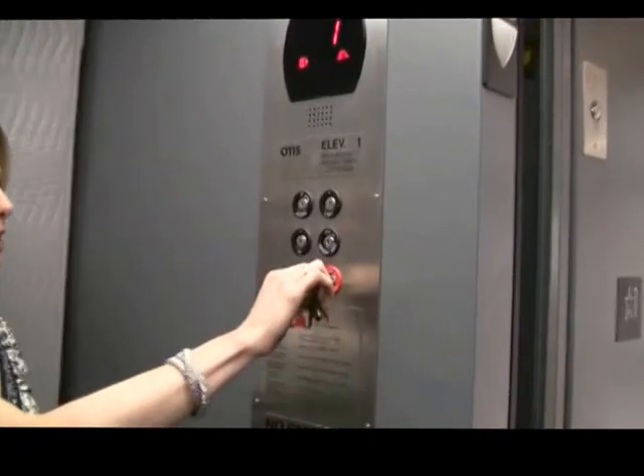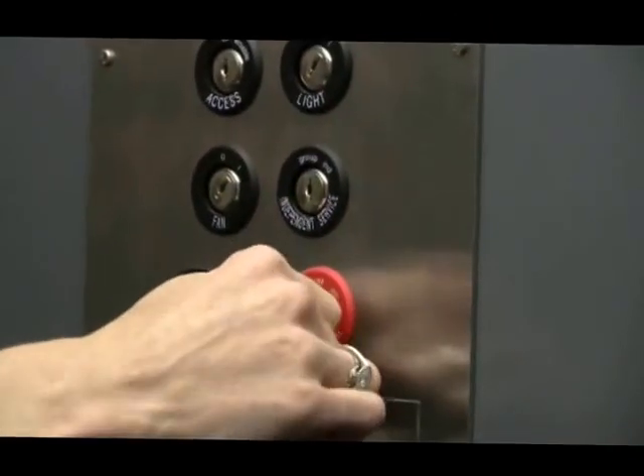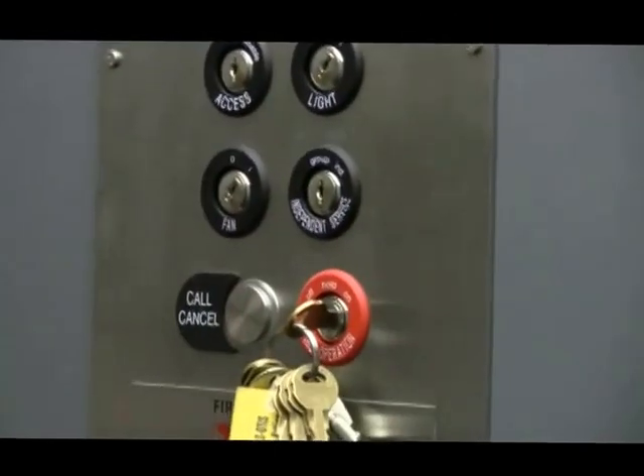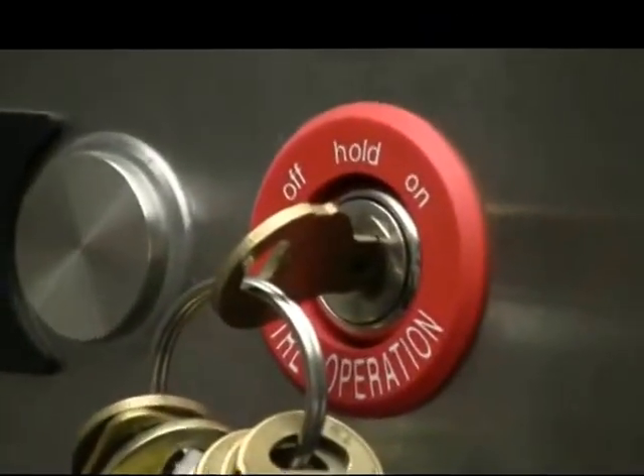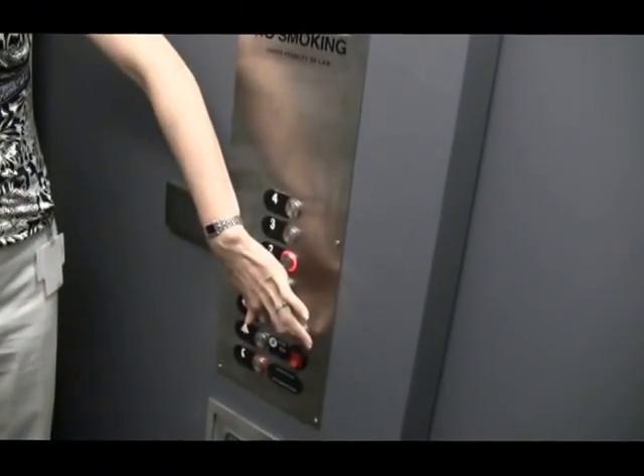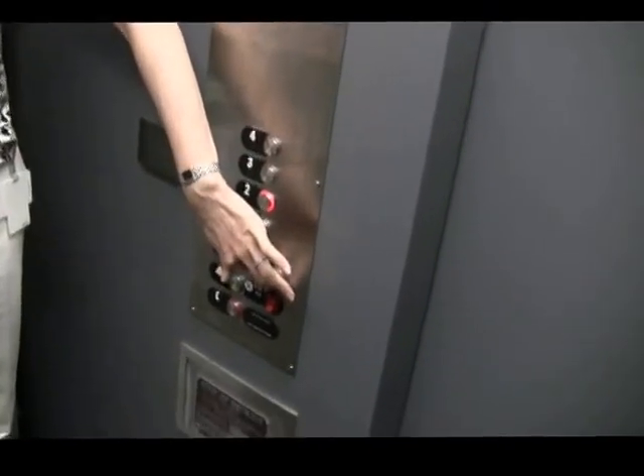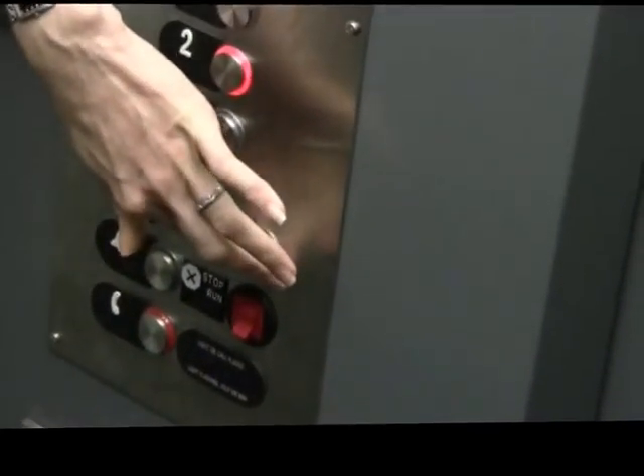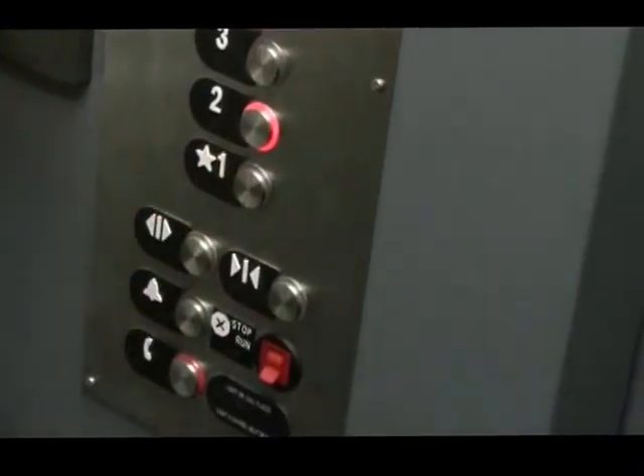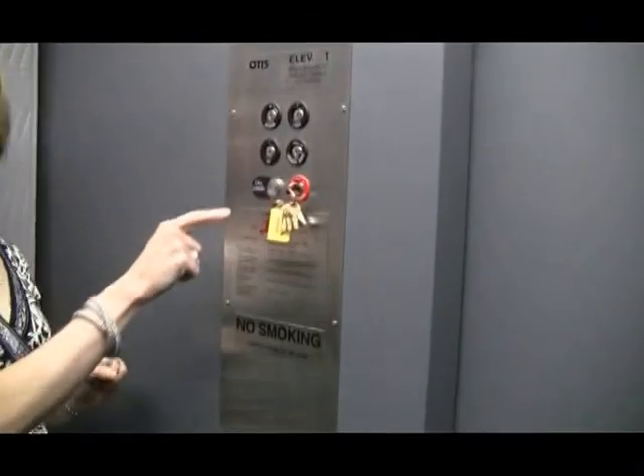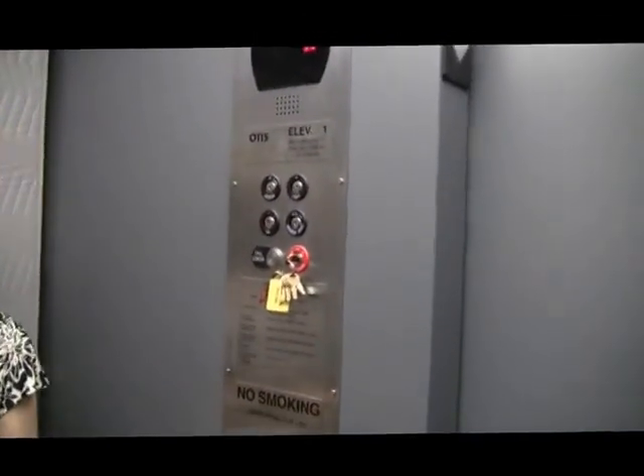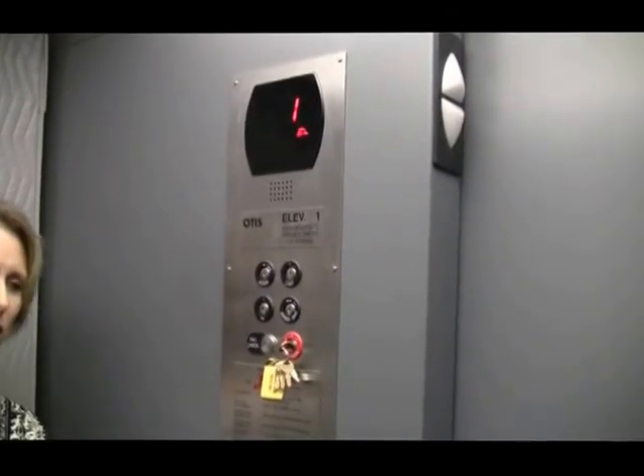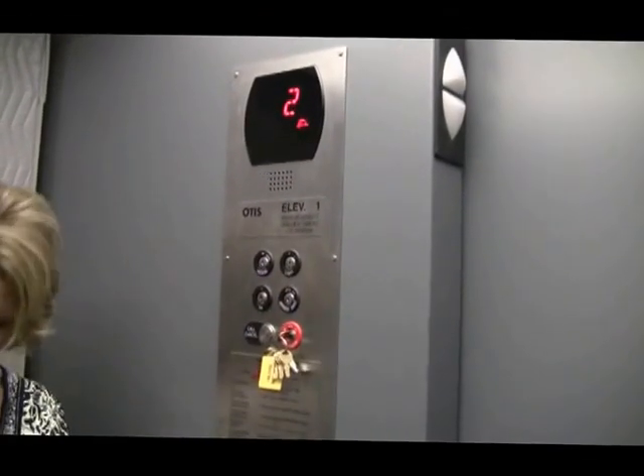And I'll just, while we're here, test this. So this is the test that we perform monthly. This is called phase 2 of your fire service testing. Phase 1 is out in the hallway. We make sure that the elevator recalls. Okay. Phase 2, and this is really used for firefighters if they have to make an emergency rescue using the elevator. I don't know which one of us that is. That one's you.